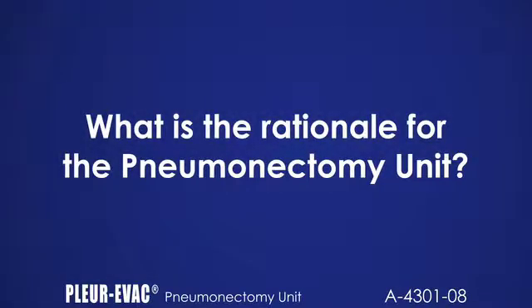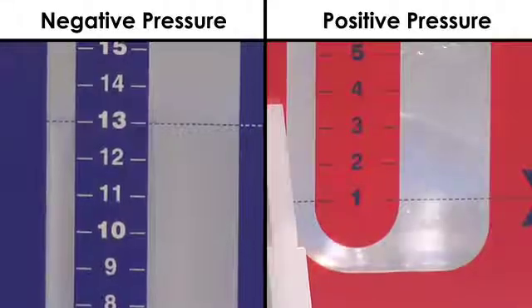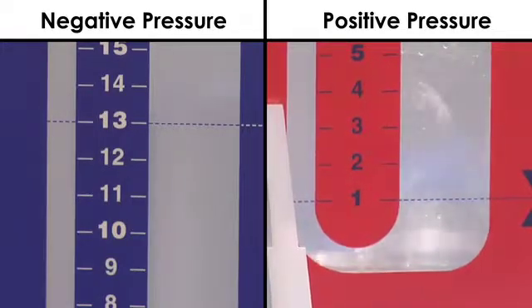What is the rationale for the pneumonectomy unit? The Pleur-Evac Pneumonectomy Unit limits the patient pressure between the levels where the negative and positive pressure columns are filled with water. The usual fill levels are minus 13 centimeters in the negative pressure column and 1 centimeter in the positive pressure column. Therefore, the patient, when attached to the unit, is limited to between minus 13 centimeters and plus 1 centimeter of pressure.